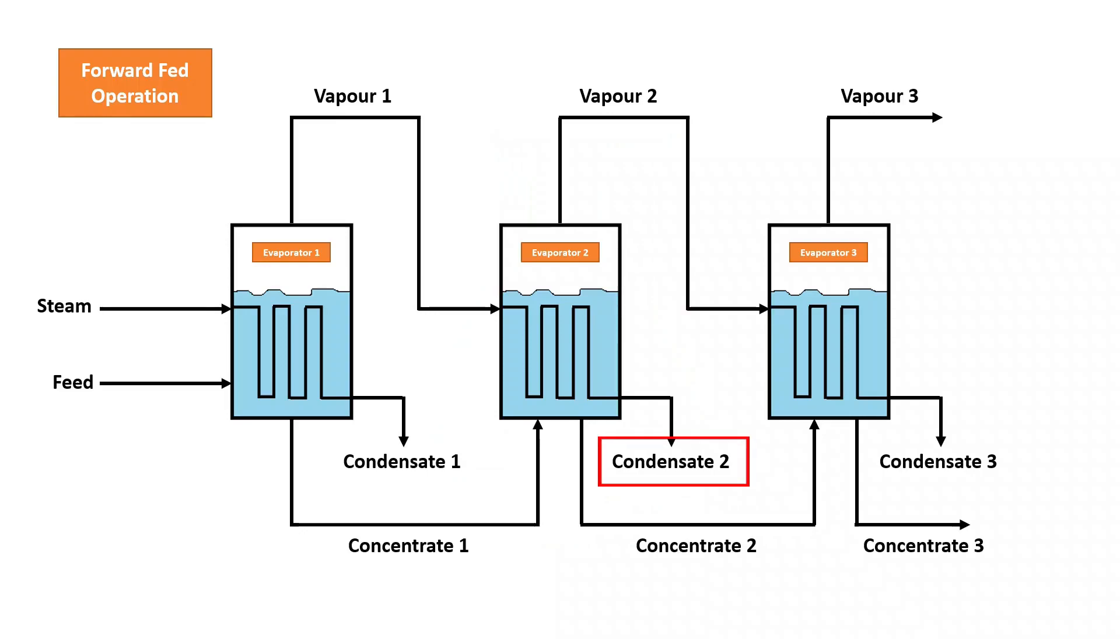Condensate leaves the second evaporator as the hot vapors in the metal tubes condense, and the concentrated product from evaporator 2 is used as the feed solution in evaporator 3, which then heats up and vaporizes to form more vapor. Condensate is also formed as the hot vapor condenses through the metal tubes. The final concentrated product from the final effect is then passed out of the evaporator.